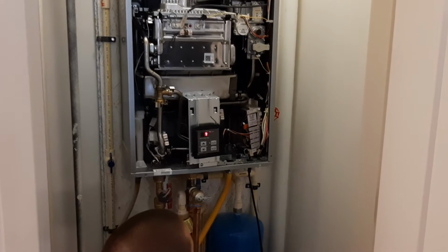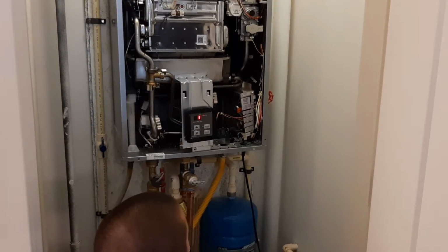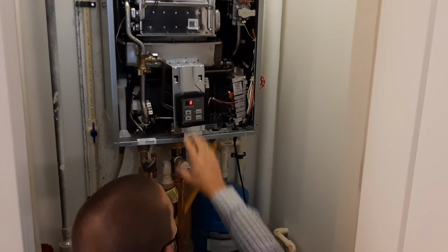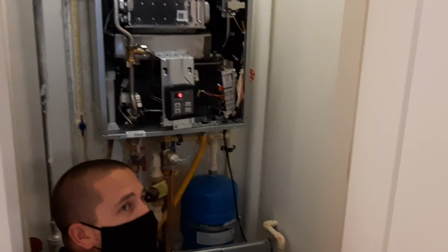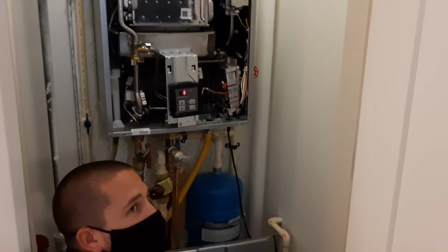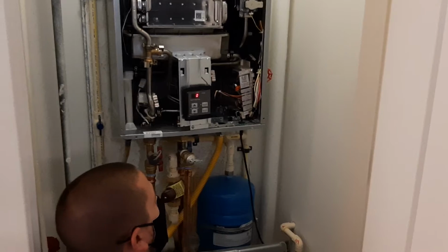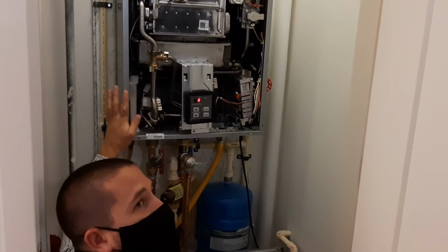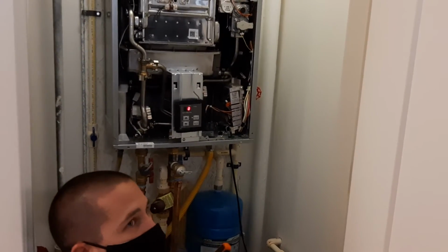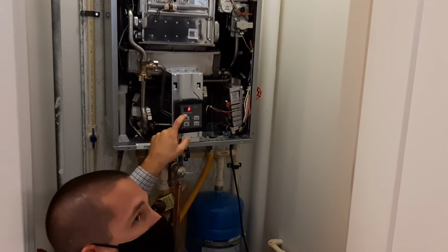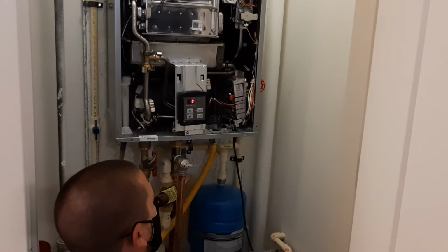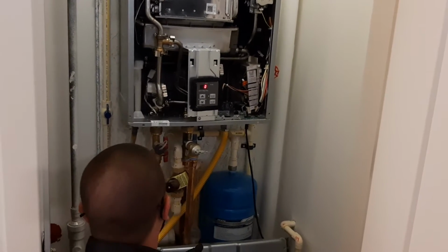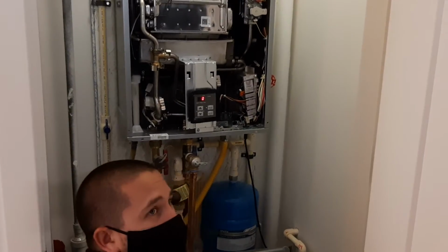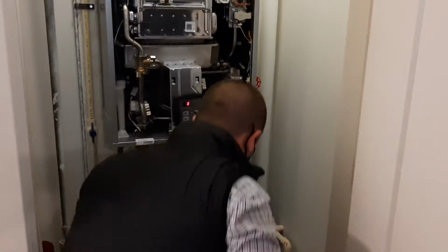Likewise, the same thing happens when somebody runs heat. Because the heat's running, the thermostat sends a signal to the air handler, which calls on and turns on its pump. The unit doesn't know if it's heat or hot water, it just knows the pump's causing flow. So you can check the flow of that pump by looking at your flow rate. That's most of it in a nutshell.